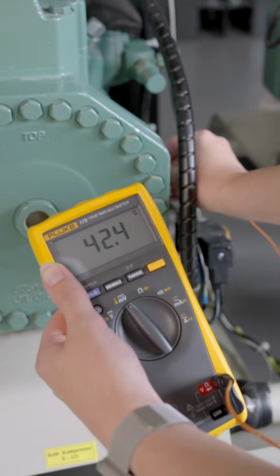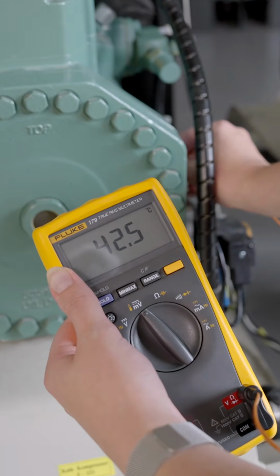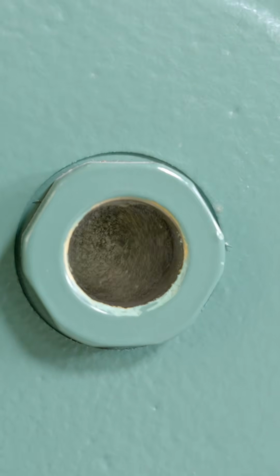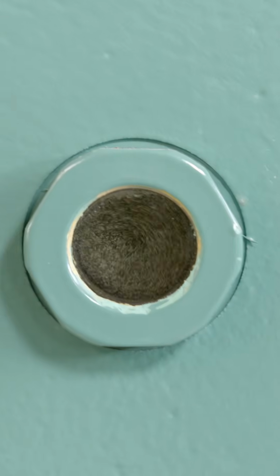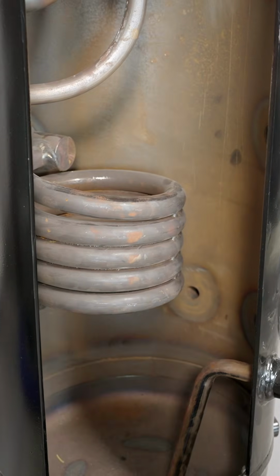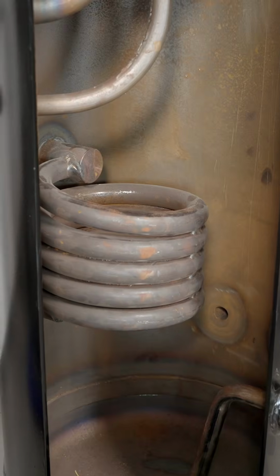The high superheat keeps the oil temperature elevated. That keeps vapor out of the oil and lubrication working. And the cool part is, the heat exchanger cools the receiver liquid and may reduce vapor saturation. Vapor saturation? That brings us to the next receiver ports.